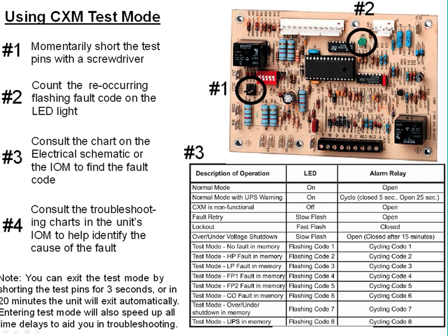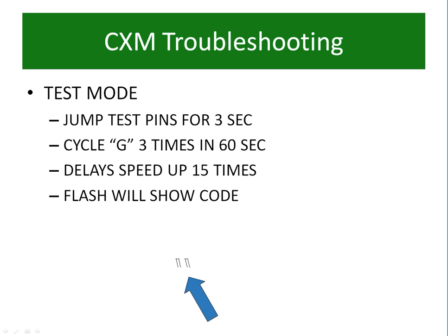You're going to see on the bottom of this screen the menu. What do the fault codes or the blinks mean? And that is adhered to the inside cover of your electrical control box in that heat pump. So to enter the test mode, to pull those faults, you can jump across those test pins, that number 1 that you just saw circled, for 3 seconds. That fault status light will go out. There will be a pause for a couple moments, and then it will start to blink the pattern. Give a pause and blink that pattern again. It'll continue to do that as long as it's in that test mode, for up to 20 minutes.